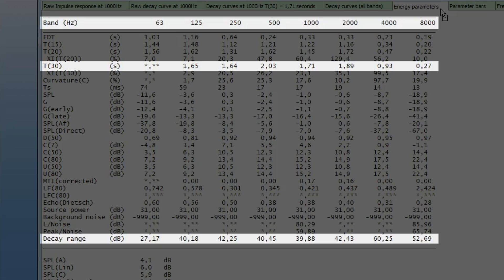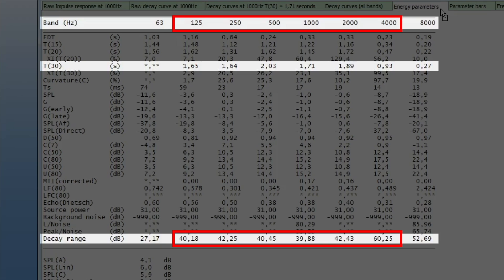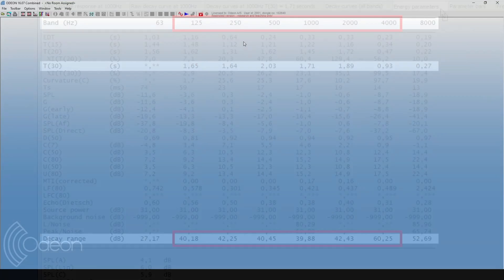However, with this microphone, this frequency band is most likely unreliable anyway. It should be enough to have a good quality measurement between the 125 Hz and 4 kHz octave bands, and look at the results mainly in those bands. Then, the impulse response can be taken to the office PC for detailed analysis.